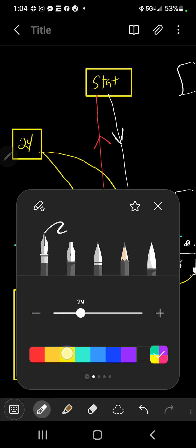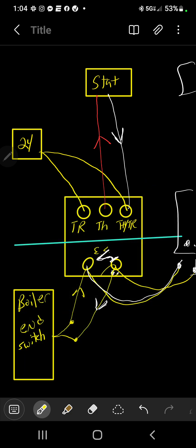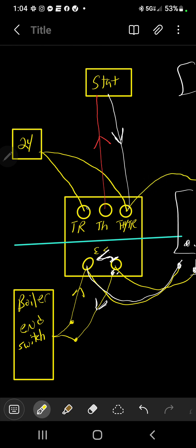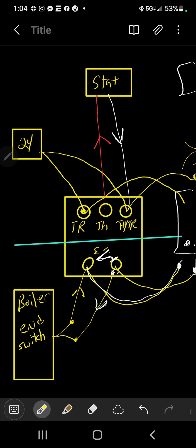If you do have another zone valve, you can do the same thing you do with the end switch. You're going to bring this wire now over to your THTR, and then you're going to bring this wire here, your thermostat, over to your TR. You're going to jump it over. And then if there's another zone, you do the same thing. You continue on and on. You should only have up to four zone valves off of one transformer. All right, hopefully that helps.